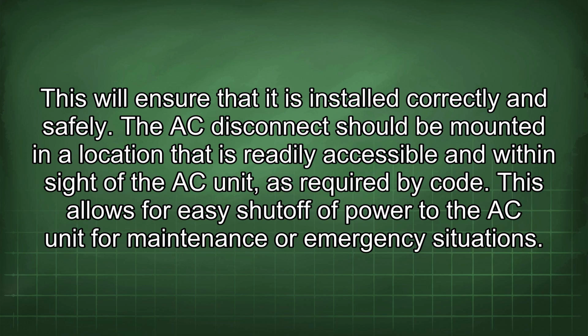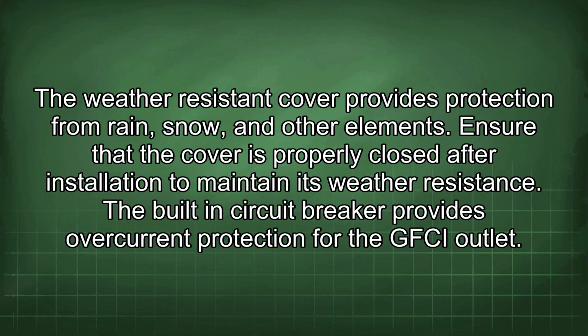The AC disconnect should be mounted in a location that is readily accessible and within sight of the AC unit, as required by code. This allows for easy shutoff of power to the AC unit for maintenance or emergency situations. The weather-resistant cover provides protection from rain, snow, and other elements. Ensure that the cover is properly closed after installation to maintain its weather resistance.